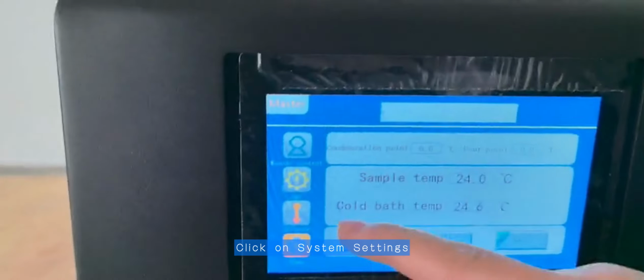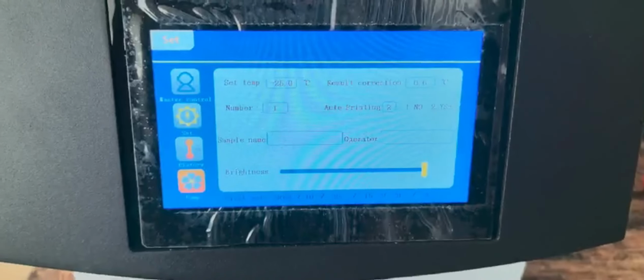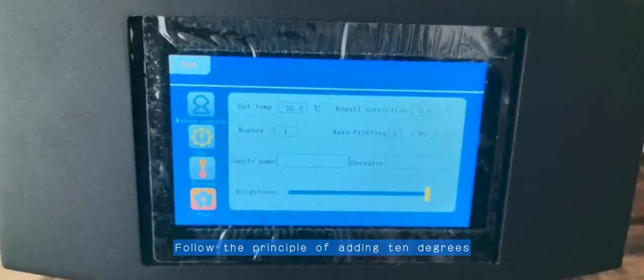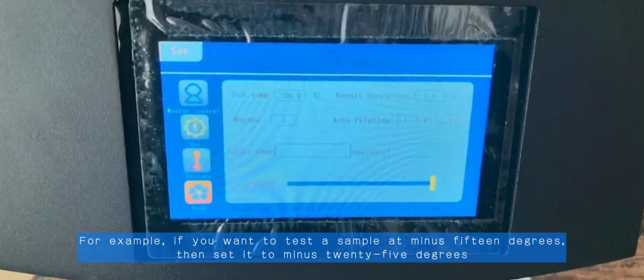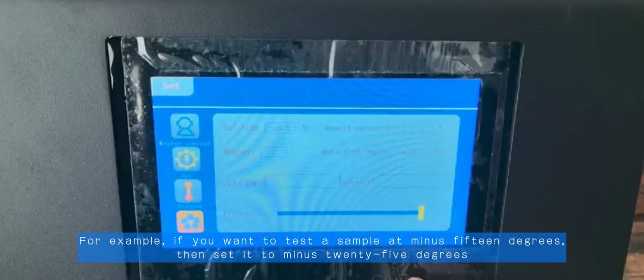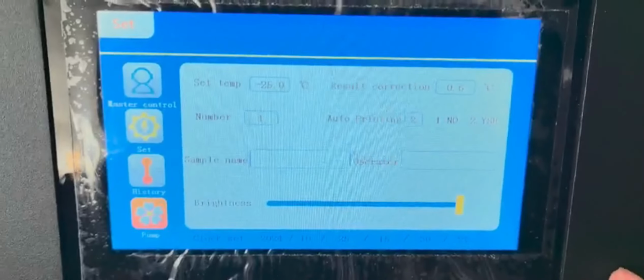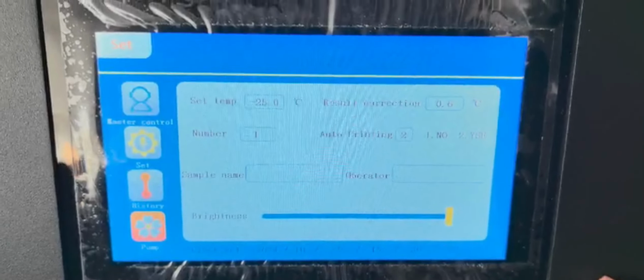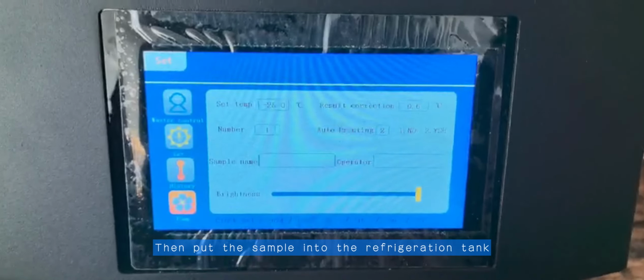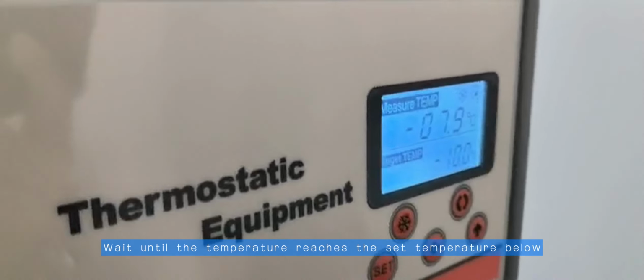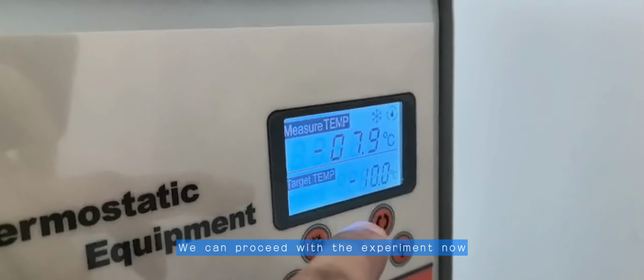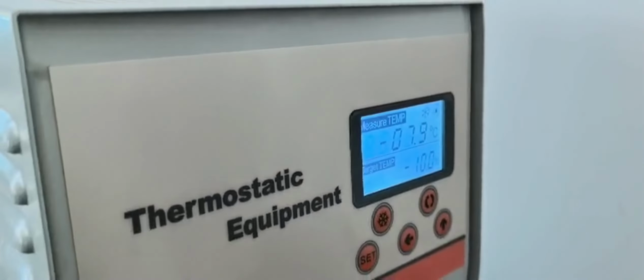Click on System Settings. According to the pour point of the sample, follow the principle of adding 10 degrees. For example, if you want to test a sample at -15 degrees, then set it to -25 degrees. Then put the sample into the refrigeration tank. Wait until the temperature reaches the set temperature below. We can proceed with the experiment now. Then just click Start directly.